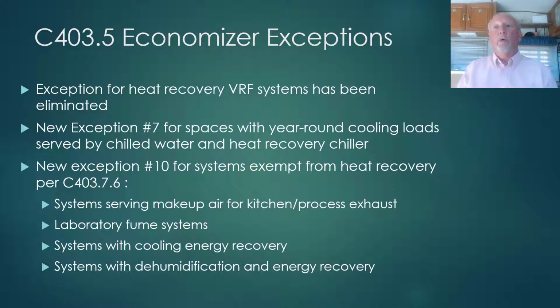You'll qualify for exception 1 with DOAS. New exception 7 is for spaces with year-round cooling loads served by chilled water systems and heat recovery chiller. This is applicable to spaces with high internal heat gains like labs, research facilities, clean rooms, biotech, where they have year-round cooling loads and can recover that heat energy through the chilled water system and transfer it to a hot water loop for heating. There is a new economizer exception number 10 for systems exempt from heat recovery. This would include systems serving makeup air for kitchen process exhaust, laboratory fume systems, systems with cooling energy, and systems with dehumidification and energy recovery.